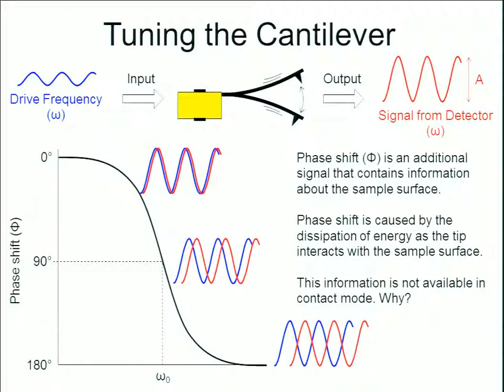Why is phase shift not available in contact mode? It's simple: in contact mode, there's no phase to be shifted. The cantilever is not vibrating — it's in constant contact. That's why we can derive this new information from tapping mode, as opposed to contact or even non-contact modes.